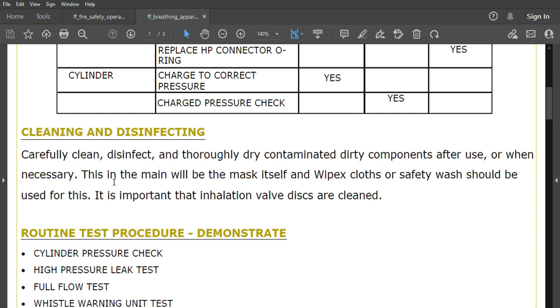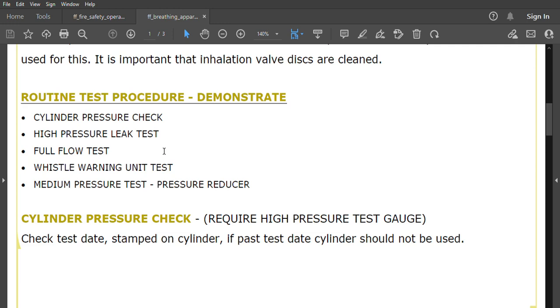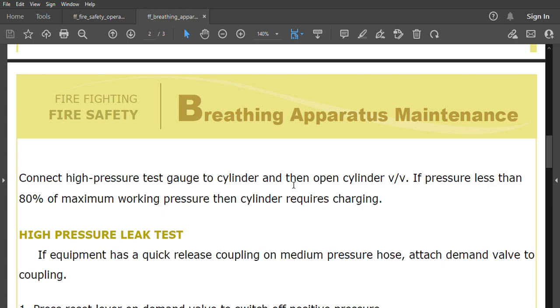When cleaning and disinfecting, carefully clean, disinfect, and thoroughly dry contaminated or dirty components after use or when necessary — this will mainly be the mask itself. Wipes or safety wash should be used. It is important that the inhalation valve discs are cleaned. The routine test procedure covers: cylinder pressure check, high pressure leak test, full flow test, whistle warning unit test, and medium pressure test for the pressure reducer.